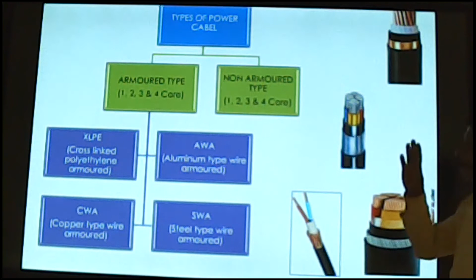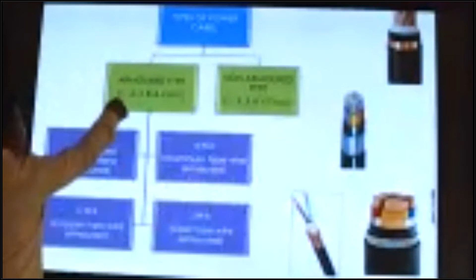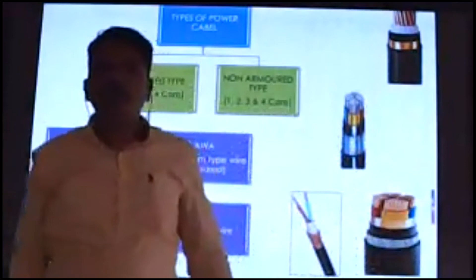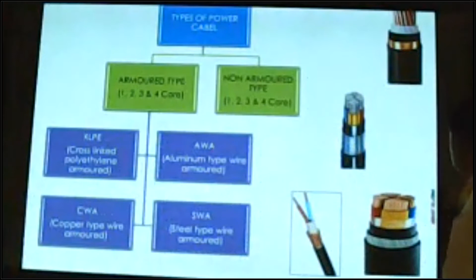We have the 4 types of armored cable: XLP, CWA, AWA, and SWA. And they are available in 1 core, 2 core, 3 core, and 4 core. Armored cable is available up to 4 core, and non-armored cable is also available up to 4 core, standard core. Okay. So you can check the armor: this is copper type, this is steel type, this is aluminum type, this is XLP type. Clear about this slide. Okay. This is an important topic, so I will recap it. Next one.